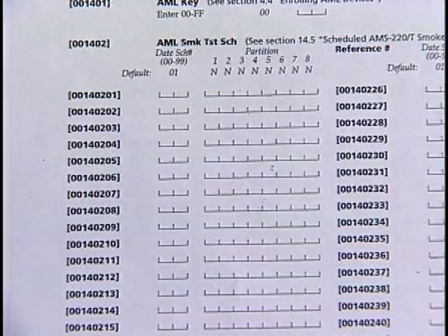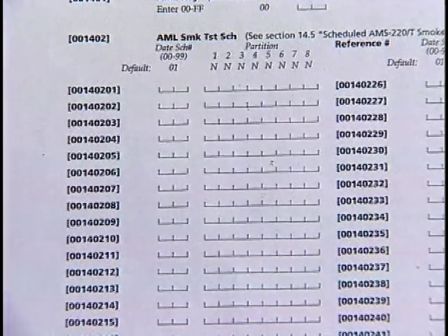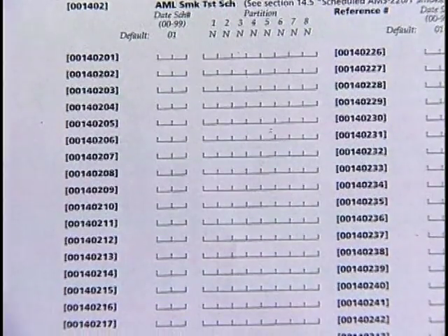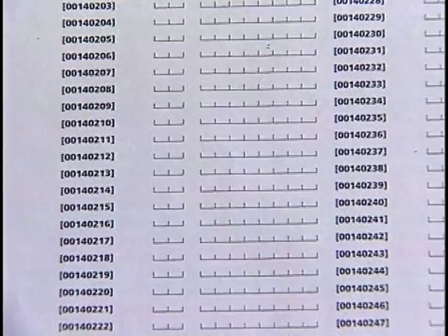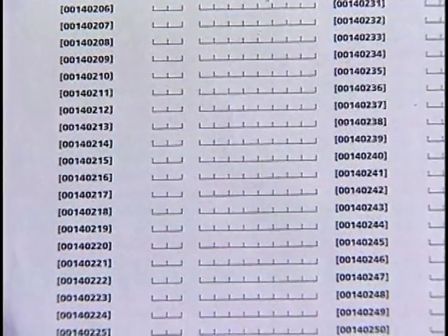The panel can also be programmed to test the addressable smoke detectors on a scheduled basis. This is identical to the manual test. If any AML smoke detector cannot properly communicate an alarm or alarm restoral to the main panel, a trouble condition will be generated.